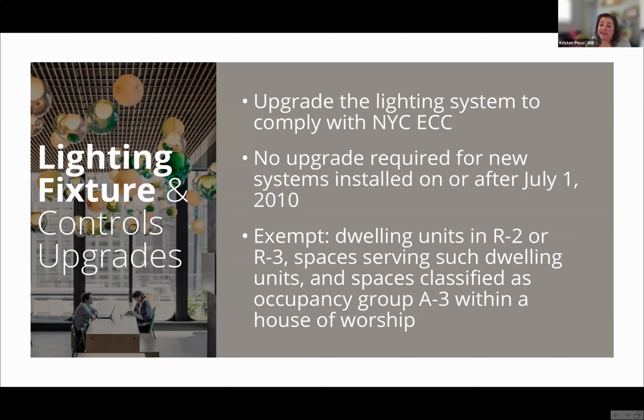Because of that, Local Law 88 states that any project filed on or after that July 1st, 2010 date does not require additional upgrade under Local Law 88, because it would all have already been in compliance based on the applicable version of the NYC ECC and the filing requirements therein. So Local Law 88 is really targeting the vast majority of spaces and buildings that were installed prior to that 2010 threshold. And therefore, those installations would not have been subject to any specific energy code requirements. So the goal is really to bring that aging existing infrastructure up to code and help reduce energy usage based on that.